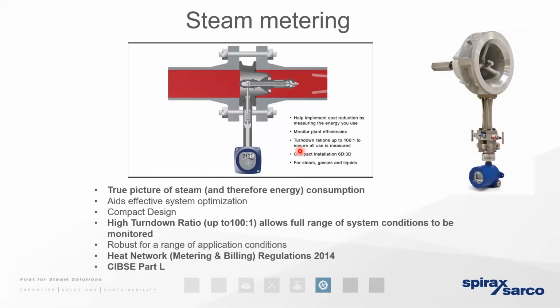We also know that certain processes, especially in building service applications such as hospitals and universities, are going to follow building regulation CIBSE Part L. That determines that if they're interfacing with an existing heat exchanger that hasn't had some attention in some time, we're obliged to follow good practice and ensure that it works efficiently. And the only way we can do that is by ensuring that whenever we are undertaking any remedial works, we do fit a steam meter to prove that it is working efficiently, or if it's working inefficiently, we're at least aware of the extent to which it is doing so.